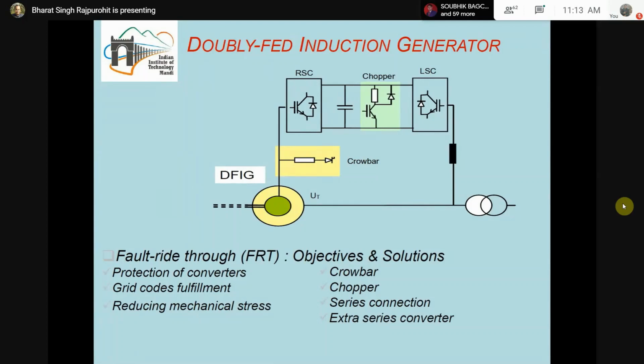Now please see, if this line side converter alone is considered, then it just acts as a static compensator or active power filter. It can act as a static compensator to provide reactive power support, as well as act as an active power filter alone also. If the control ability is provided, then it can address the power quality as well as the reactive power also. So this is the line side converter. Its rating should also be augmented to have this control option.